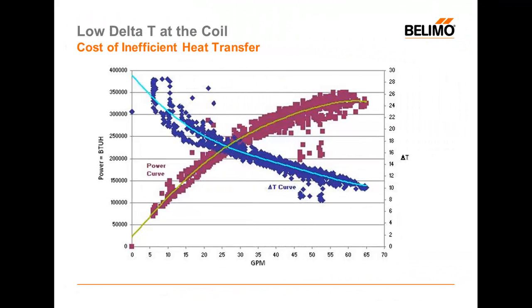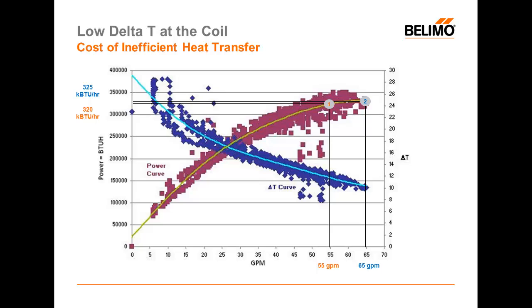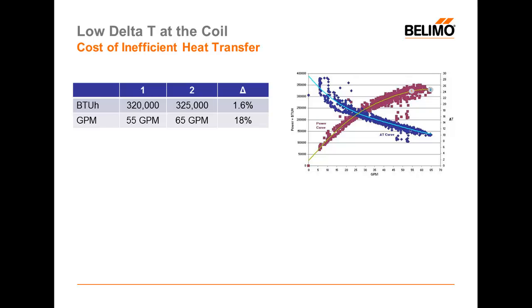Let's take a look at the cost associated with controlling at those two points. Point 1 uses about 55 gallons a minute and achieves 320,000 BTU. Point 2 uses about 10 gallons a minute more and achieves about 5,000 more BTUH into the space. So we have a very small increase in BTU while percentage-wise a fairly large increase in flow. If we examine this on a chart, it takes 18% more GPM and nets us just 1.6% more BTU.